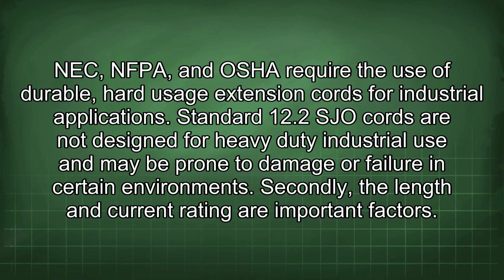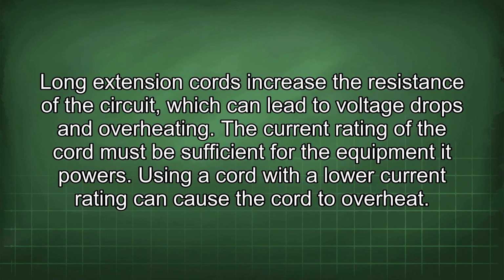Standard 12.2 SJO cords are not designed for heavy-duty industrial use and may be prone to damage or failure in certain environments. Secondly, the length and current rating are important factors. Long extension cords increase the resistance of the circuit, which can lead to voltage drops and overheating. The current rating of the cord must be sufficient for the equipment it powers. Using a cord with a lower current rating can cause the cord to overheat.